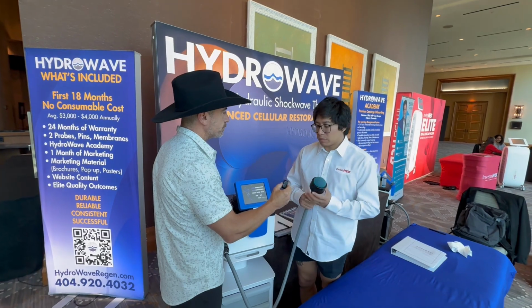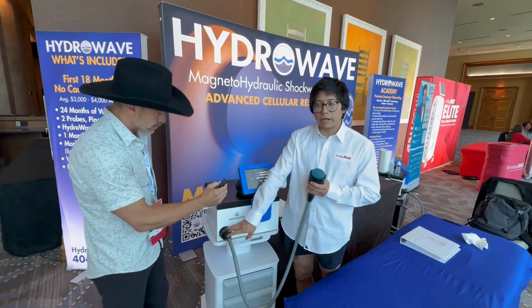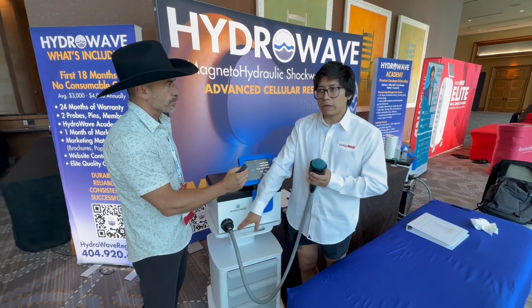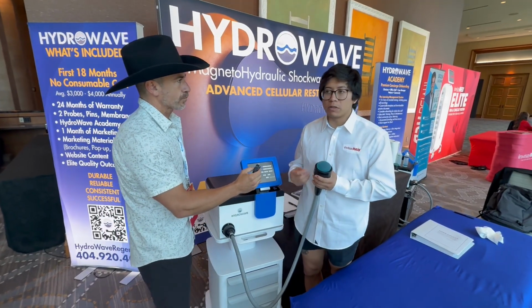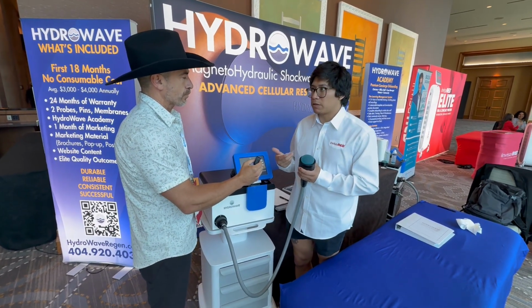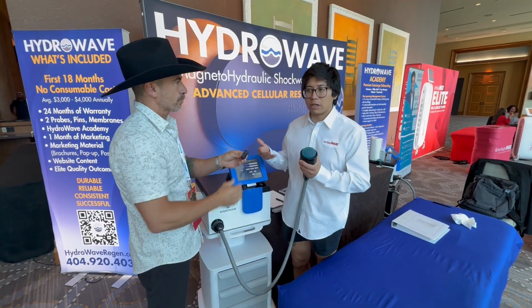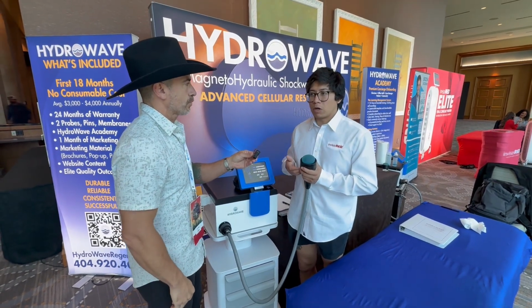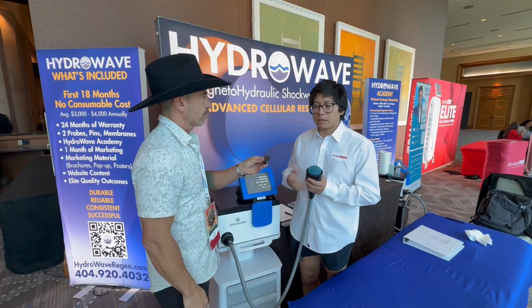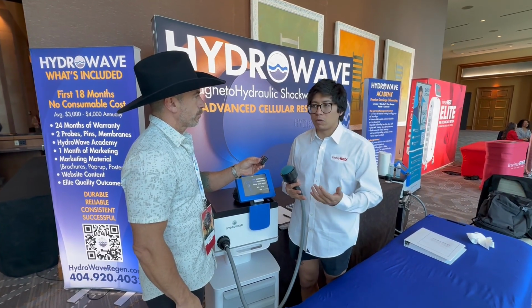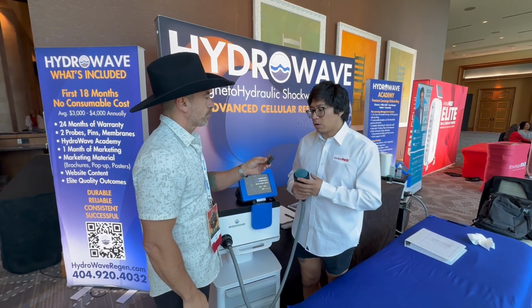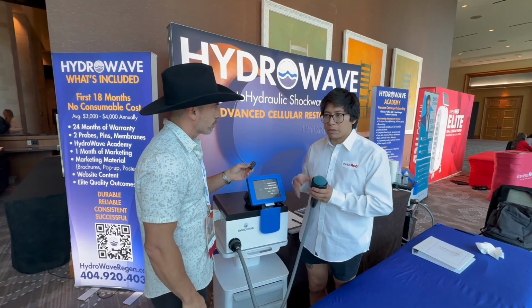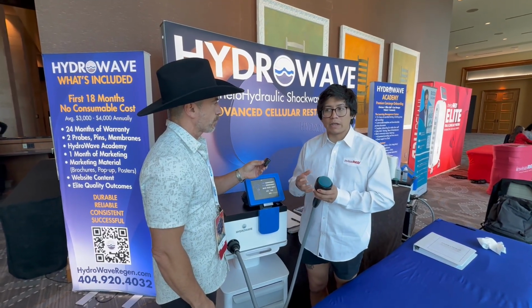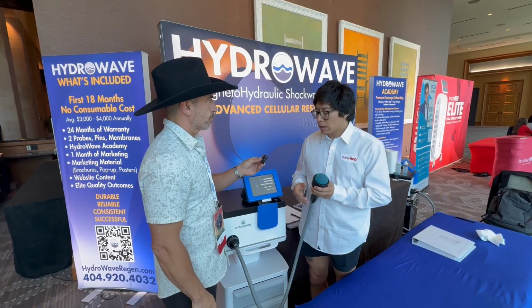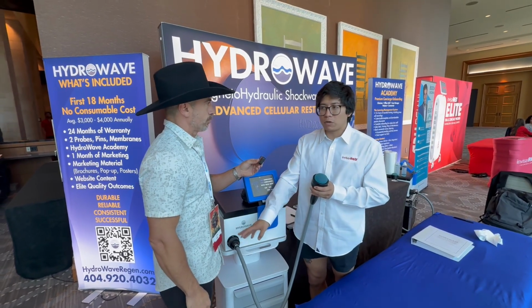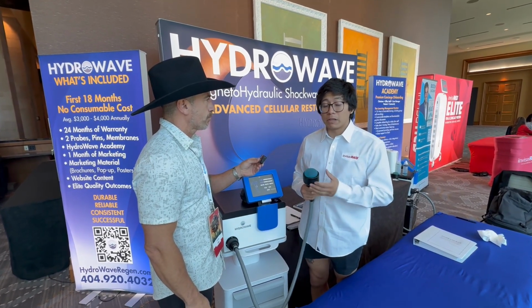What we've seen is some shorting right here happening in the pin section, which is why we include extra pins with each purchase. You just go in there with a Phillips screwdriver, take out the old pins, and put the new pins in. That happens because the amount of energy coming through there will cause oxidation, basically the metal being broken down. That's just normal stuff that happens in electronics. Because we're using a lot of energy to create that shock wave for the therapeutic modality, we sometimes have to replace it. Those pins last 500 to 1 million shots.